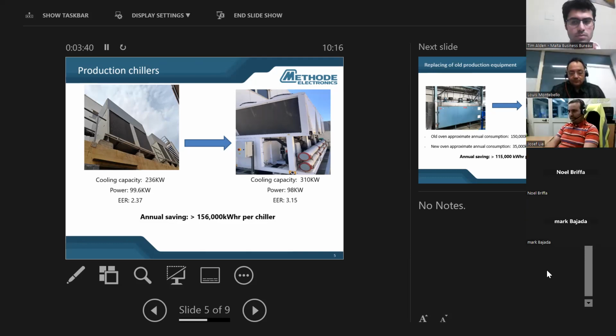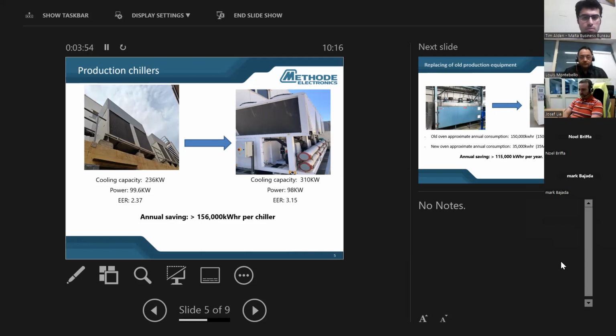We have compared the EER. If we see the old chillers, basically they had a cooling capacity of 236 kilowatts with an EER of 2.37. The new chillers have a cooling capacity of 310 kilowatts and an EER of 3.15. Apart from that saving, the old chillers had one evaporator, and therefore the saving that we're going to achieve is much, much higher than what we are showing over there.